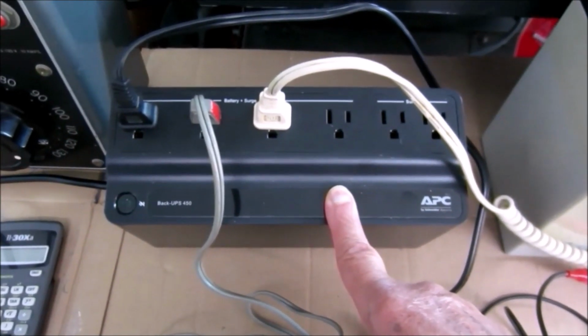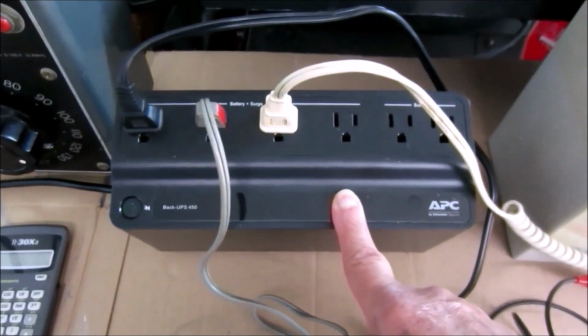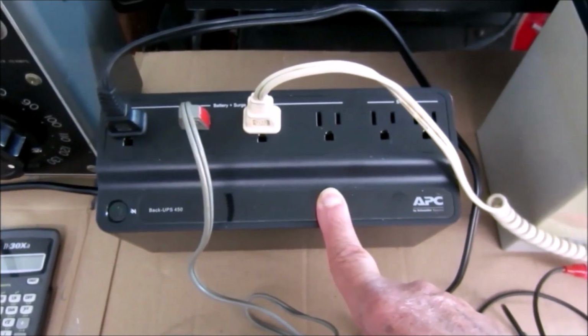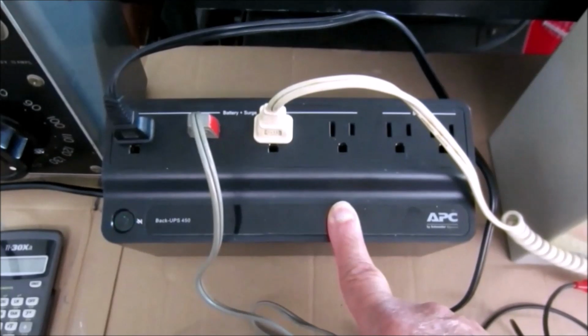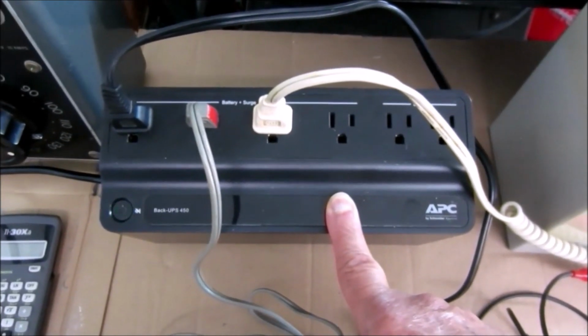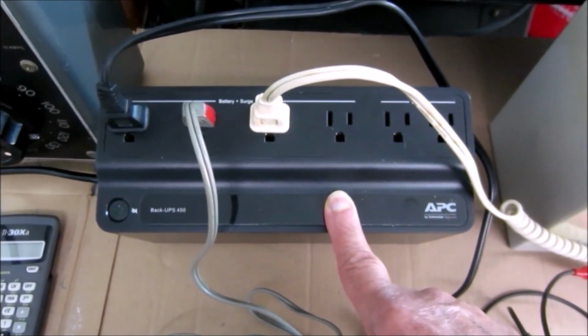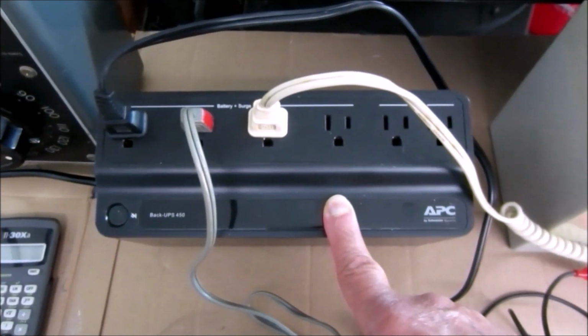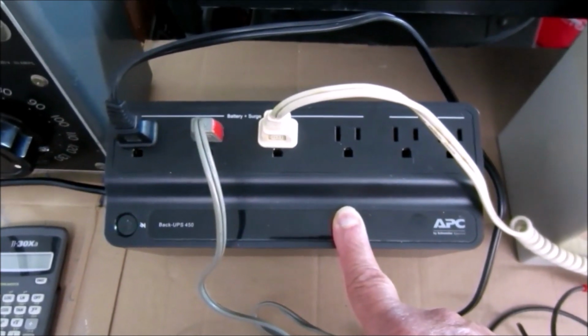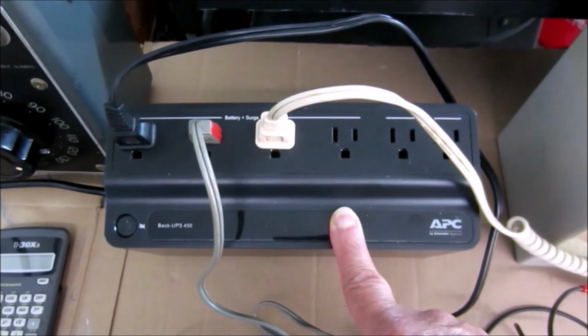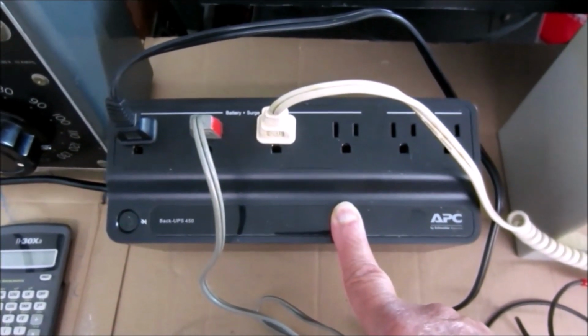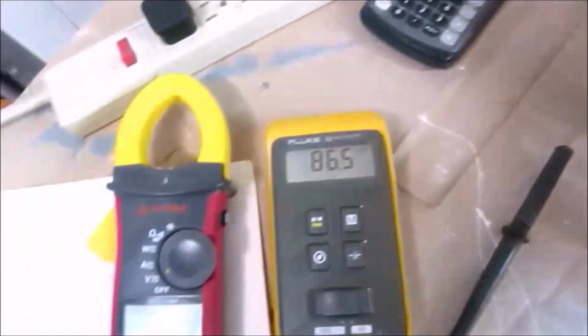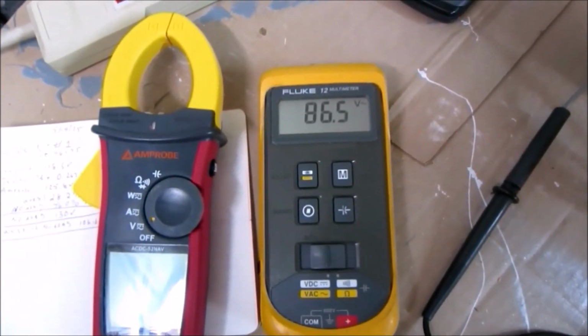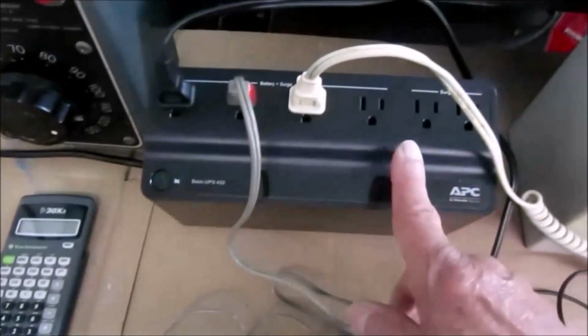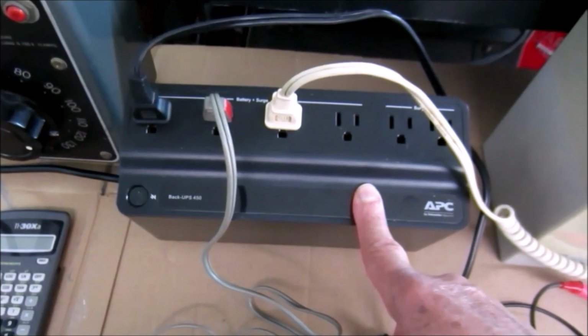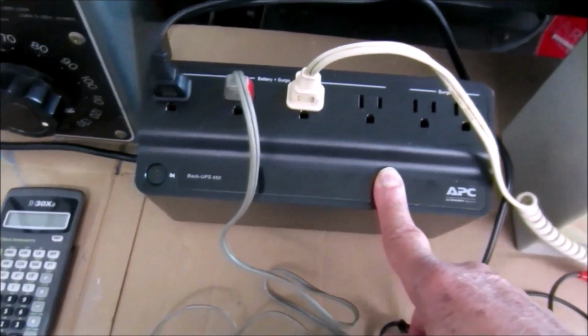It's supposed to be an uninterruptible power supply. I would think that any reasonable person would expect it to deliver power within the US range of, say, 110 to 124 volts, because that's what we have here, 117 plus or minus 7 volts. We are way out of range here. This is a brownout, not suited for the purpose to which it's intended.